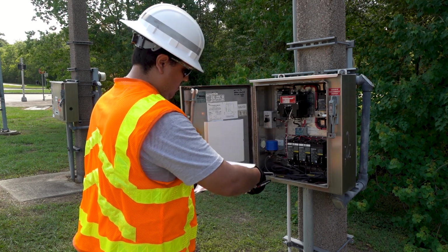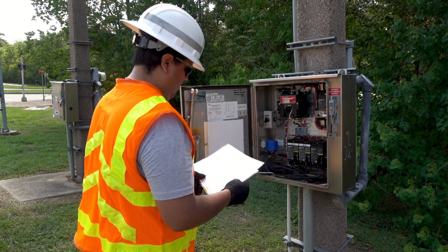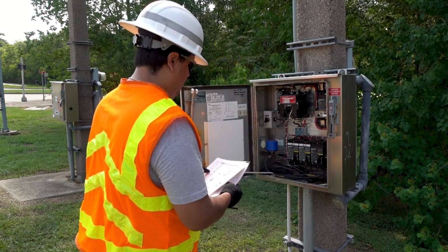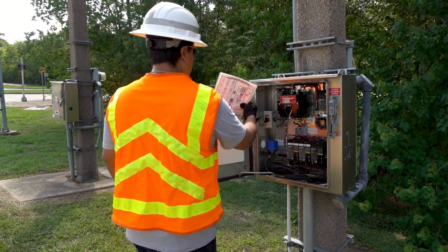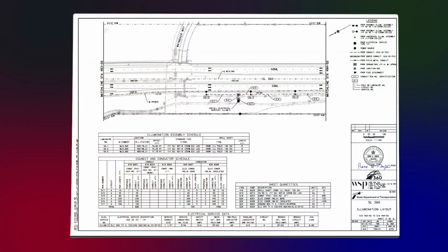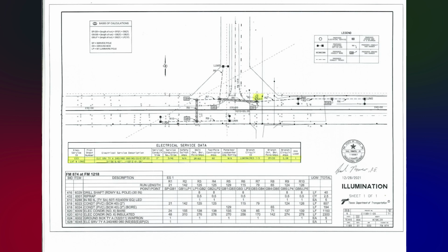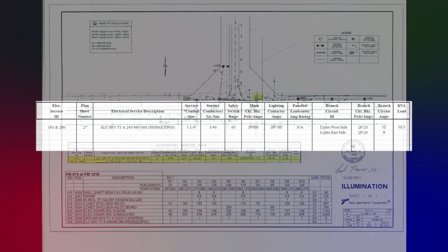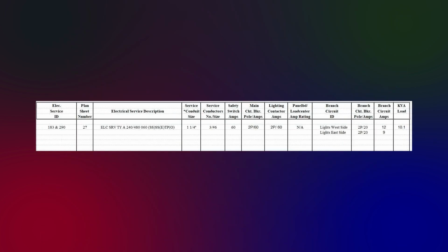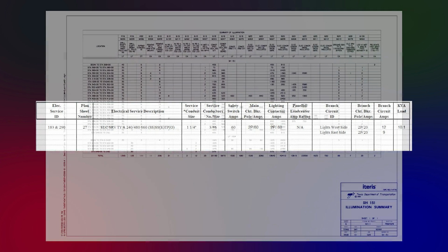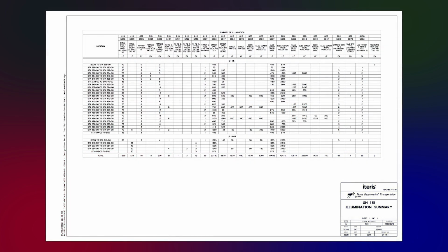The UL 508 shop must also include a laminated plan sheet from the project with the electrical service data chart used to build the enclosure shown on it. Other documents required are the electrical plan sheets, redlined with any changes made in the field, reduced to 8.5 by 11 inches, and laminated. These plan sheets should show the location of every branch circuit from beginning to end that is fed from the electrical service that is being inspected. These drawings will help maintenance personnel troubleshoot the system in the future.